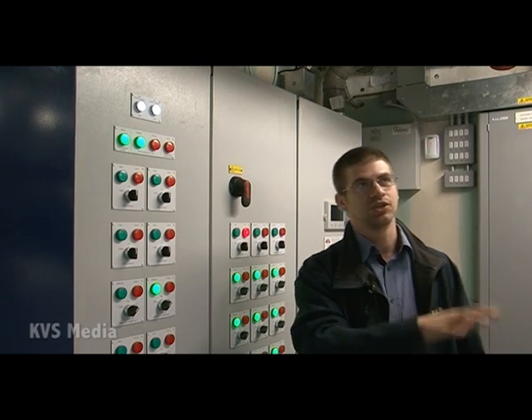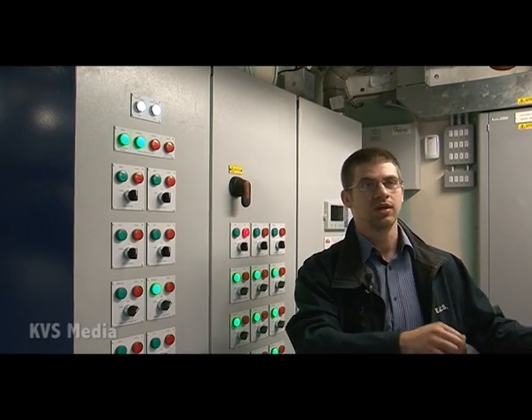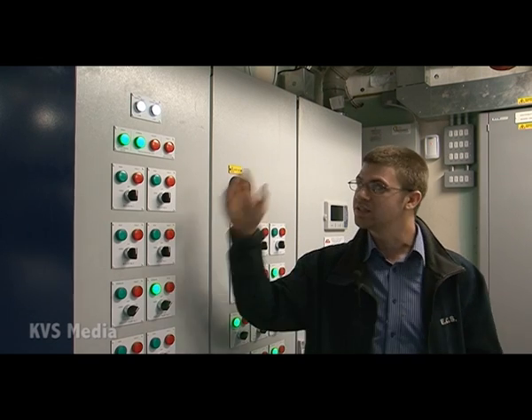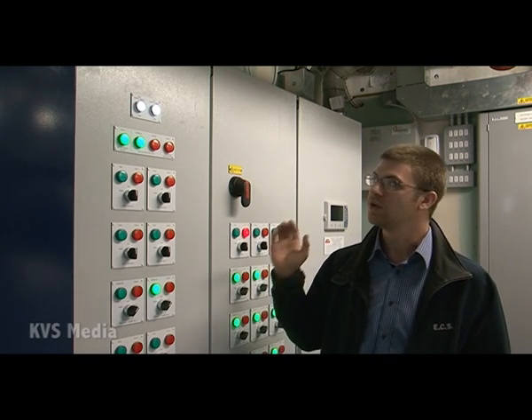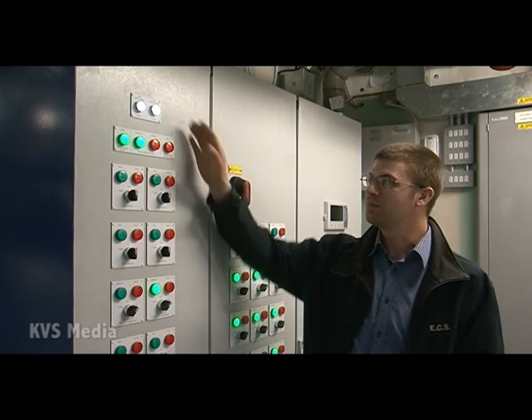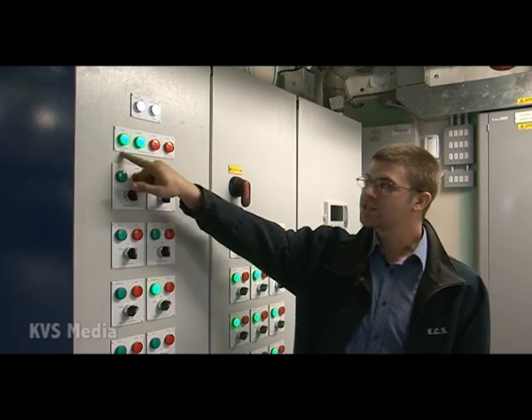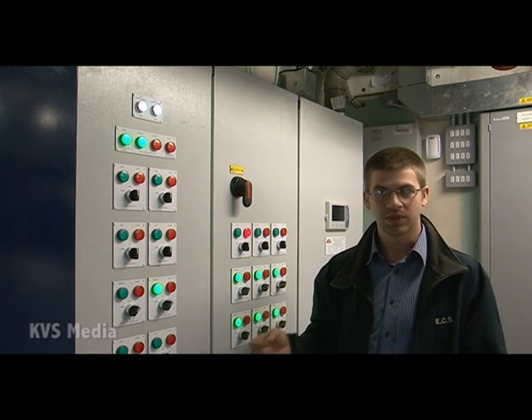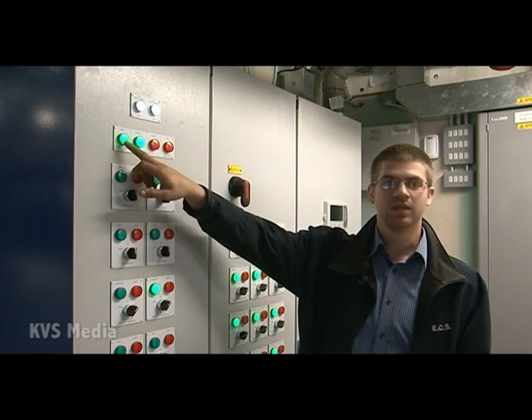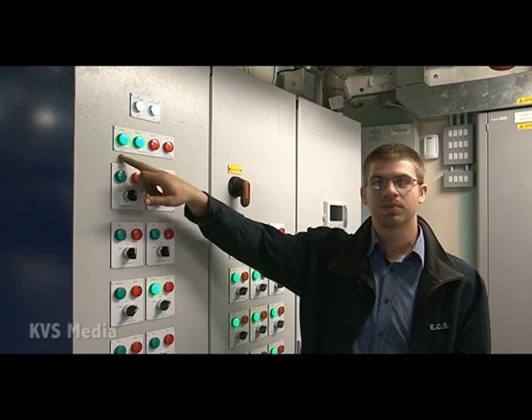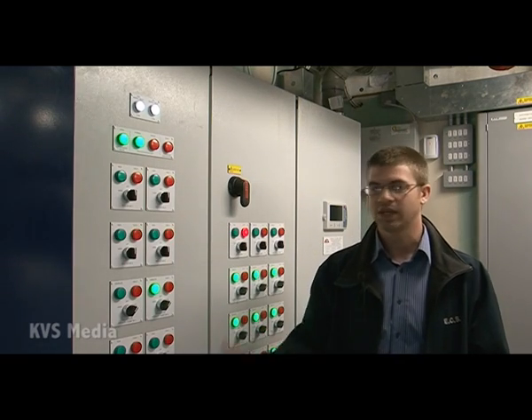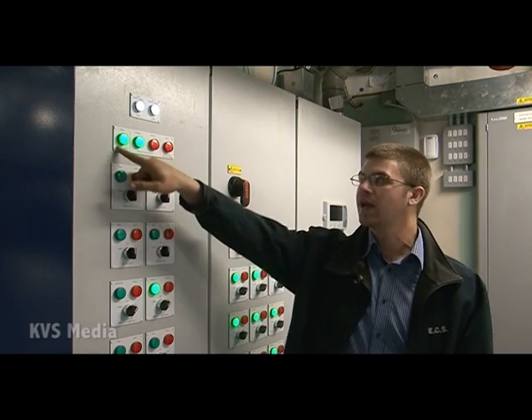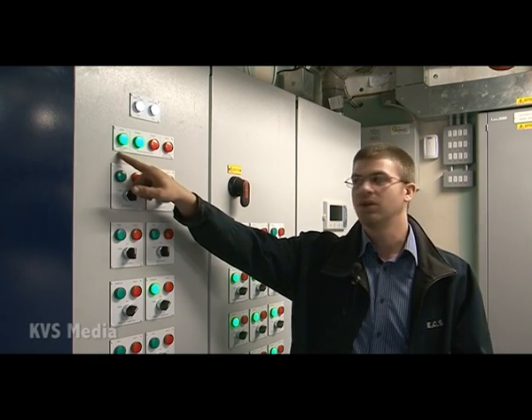There's some fire detection equipment in here above the boilers. If flames are detected, this will switch off. So there's a fairly major problem if they're off. The gas valve, which is providing gas to the 4 boilers and the CHP, has got a limit switch on it, so it will tell you when it's open. There's also indication on here telling you that the gas valve is open, so if the boilers go off for any reason, the CHP goes into a fault and you come in here and the gas valve isn't open, you know that again you've got a fairly serious problem.